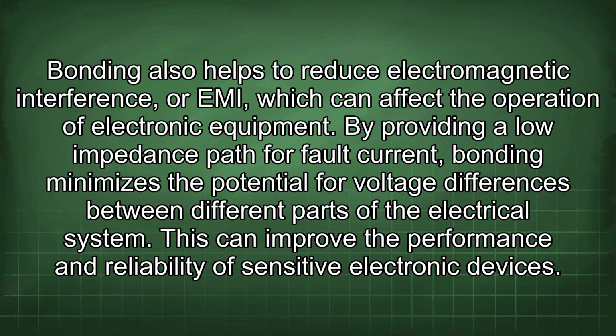Bonding also helps to reduce electromagnetic interference, or EMI, which can affect the operation of electronic equipment. By providing a low impedance path for fault current, bonding minimizes the potential for voltage differences between different parts of the electrical system.